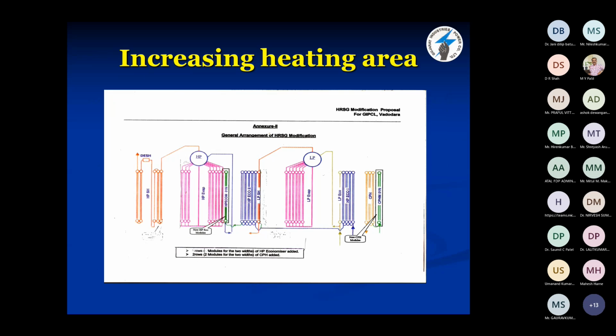You can see some of the drawings. This is the circuit of the boiler. The flue gas will enter from here. This is the HP superheater area, superheater 1, superheater 2. Then comes the HP circuit, that is the HP evaporator. This is the HP top drum, and this is the HP mud drum. These are the connecting pipings. This is the downcomer. Now this is the HP economizer. From the HP circuit, it then comes to the LP circuit. These are the LP evaporator tubes. This is the LP downcomer. Then comes LP economizer 1. Then this is the final CPH, that is the condensate preheater, and then comes the stack.